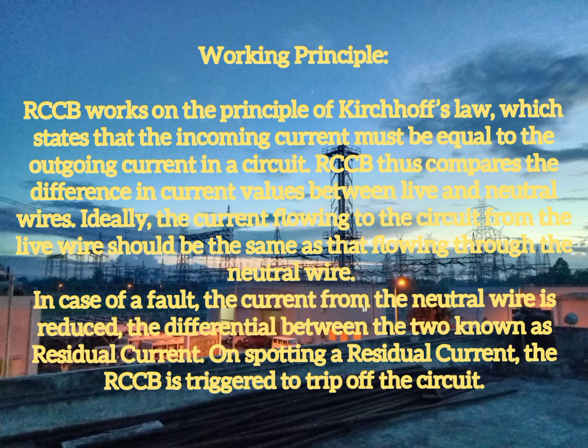In case of any fault, the current from the neutral wire is reduced. The differential between the two known values is the residual current. On spotting a residual current, the RCCB gets initiated and triggers the tripping circuit, and the trip will happen by the RCCB circuit.